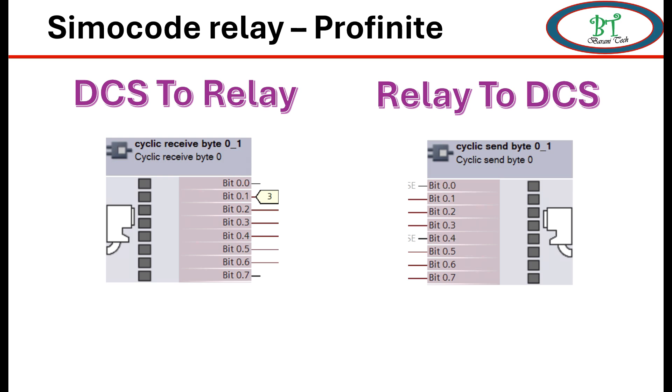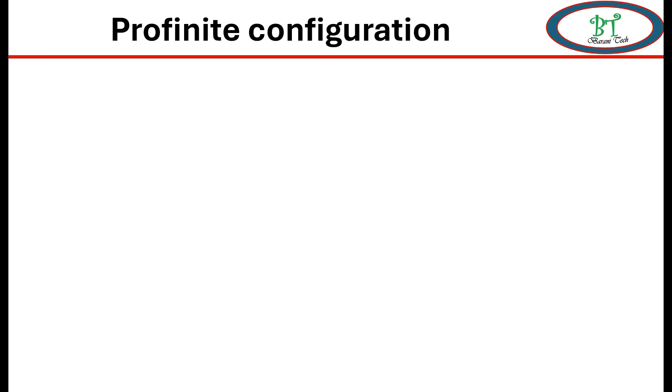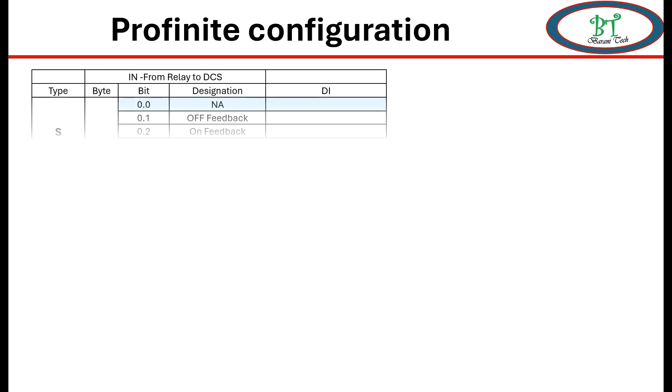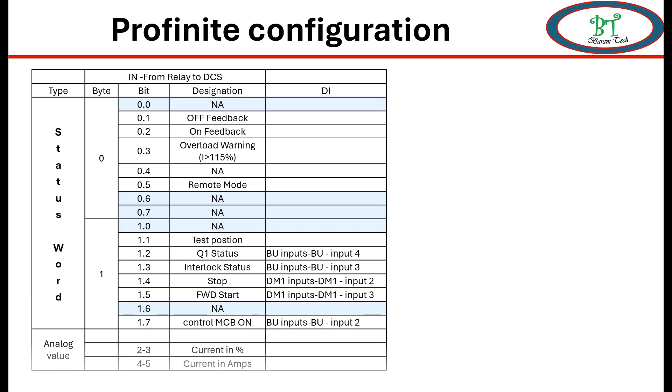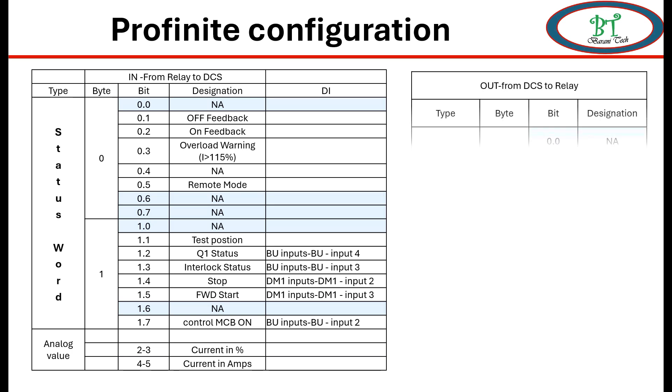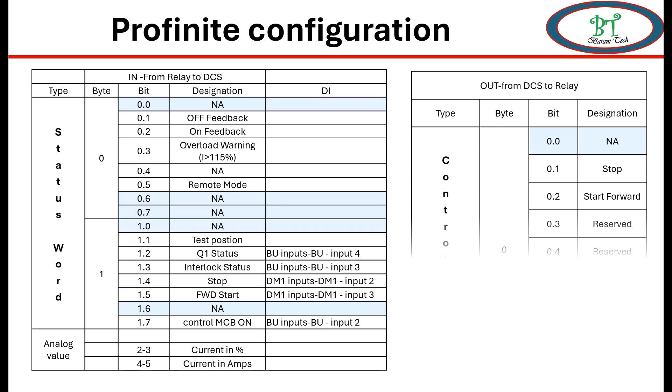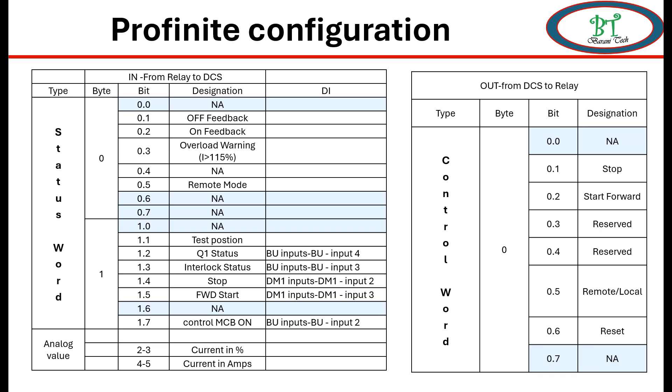Second, we need to know about all signal which need to be configured for DCS. For example, I have shown the signal list for DCS. For Relay to DCS, the signals are: bit 0.0 there is no configuration, 0.1 is off feedback, 0.2 is on feedback, 0.3 is overload warning, 0.4 is none, and 0.5 is remote mode. This needs to be configured on corresponding send bit. Then only PROFINET will be able to receive the signal from the relay.